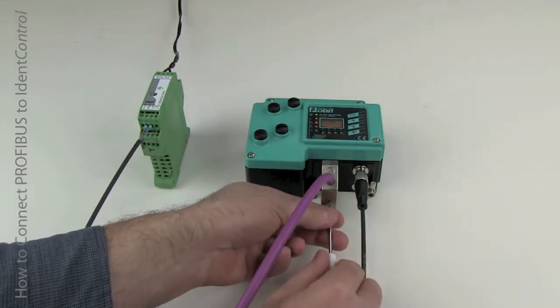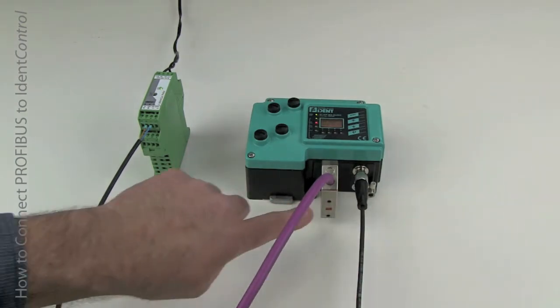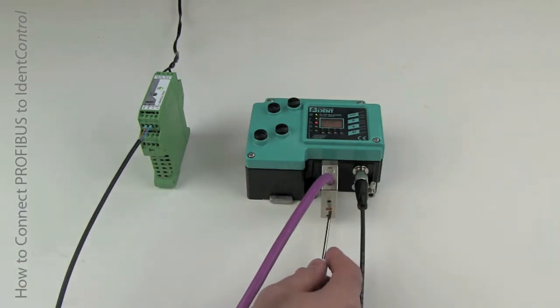If this is the last node of the network, you can see, like here, there's only one Profibus in connection, and I'm going to flip the termination switch to the on position.